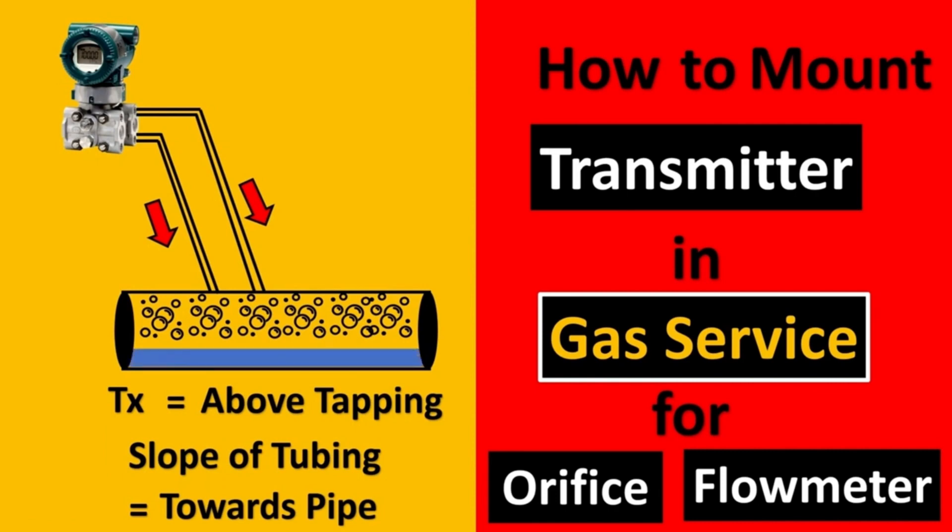What is the use of this? If the gas service also has some liquid entrainment in it, you would not want that to get trapped in your impulse lines. Because of gravity, the fluid is always going to go downward and remain in the pipe, and it won't be a dead leg for the transmitter.